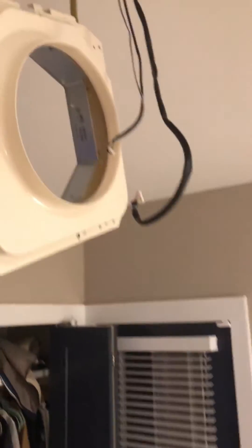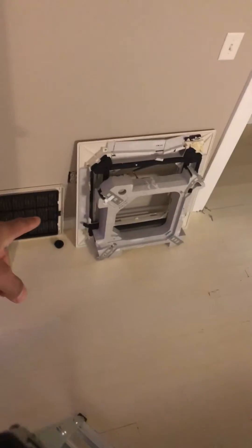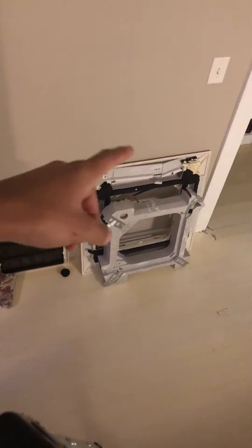I just wanted to show you my little problem here. The float switch got the drain pan, and the thing — taking off the styrofoam — cracked. Anyway, this is what these things look like. Here's a condensate pump, and here's the float switch.